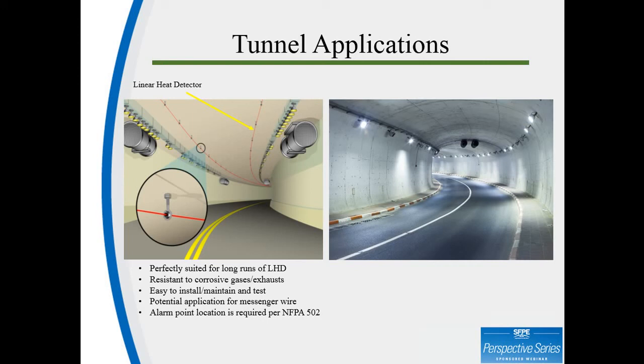Tunnels are a perfect application for digital linear heat detection. The often long runs can be easily covered by the extended zone lengths offered with linear heat detection. We recommend supporting the detector with a mounting accessory every 5 feet. Given the potential difficulty in mounting in tunnels, this can be an application for messenger wire. Messenger wire is a high tensile strength wire that can be connected using turnbuckles. This enables you to place your mounting supports 30 to 50 feet apart rather than every 5 feet.